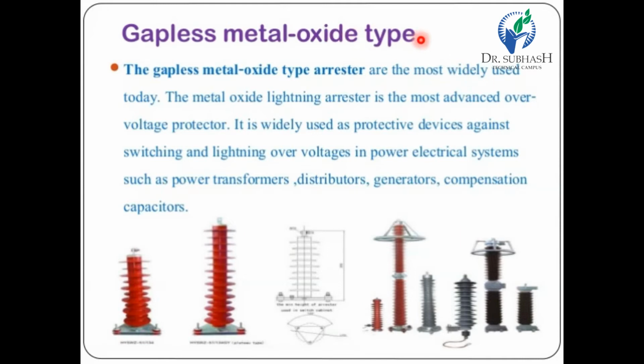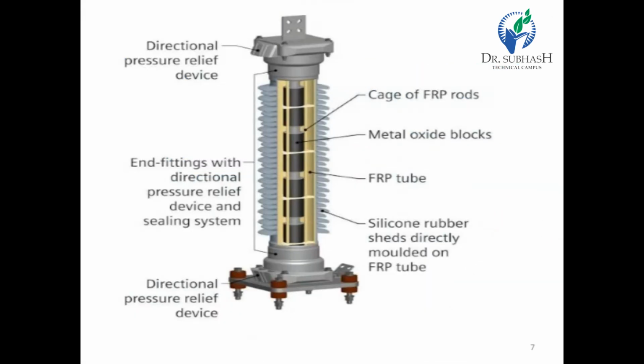Now the gapless metal oxide type arrestor. The gapless metal oxide type arrestor is the most widely used today. The metal oxide lightning arrestor is the most advanced overvoltage protector. It is widely used as a protective device against switching and lightning overvoltages in power electrical systems such as power transformers, distributors, generators, compensation capacitors, etc. It means almost all the equipment in the substation is protected through this device. These are the images of typical gapless metal oxide type arrestors.